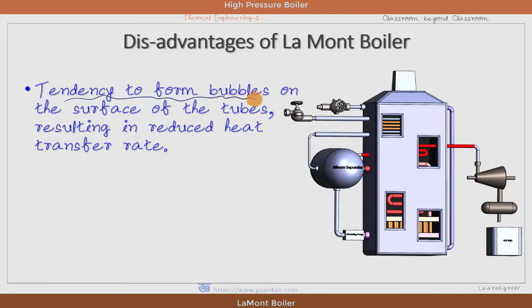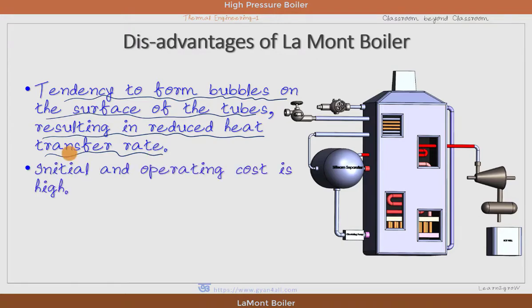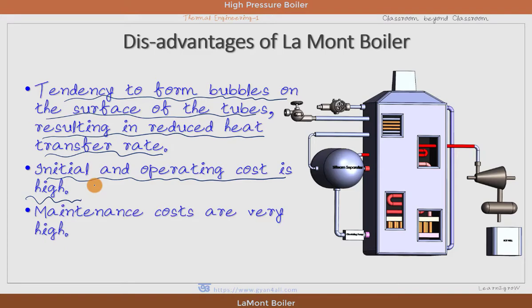There are a few disadvantages of the Lamont boiler. There is a tendency to form bubbles on the surface of the tubes, resulting in a reduced heat transfer rate. During the formation of steam within the water tubes, bubbles form and act as a barrier for heat transfer from the tubes to the water. The initial and operating cost of the Lamont boiler is higher because it produces high pressure, high temperature steam at very high capacity. Maintenance costs are also very high due to the high pressure, high temperature steam production.